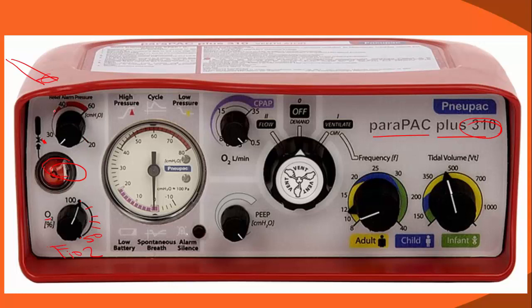Right here, we want to make sure that we're setting a relief alarm pressure. This is in centimeters of water, and our best pressure is going to be somewhere around 20 centimeters of water. If you go further than 20 centimeters of water, you increase the risk that we're going to create barotrauma, or if this is like a BVM, the risk that we're going to send oxygen into the stomach. So we generally want to set the alarm somewhere between 30 and 40. When there's high pressure in the system, for a few reasons, as we troubleshoot on the next slide, the alarm will sound and you'll know that you need to troubleshoot and fix the pressure before barotrauma occurs.